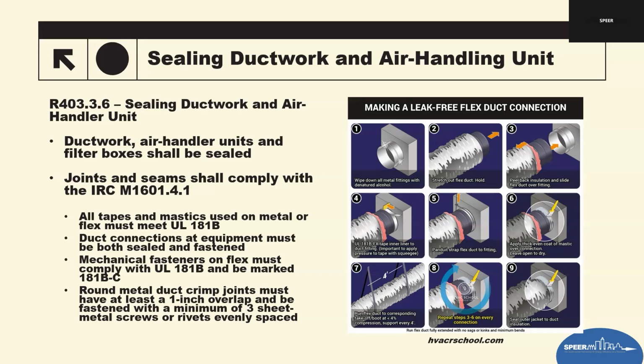So sealing alone is not enough. The joint must also be physically secured. Mechanical fasteners on flex duct must comply with 181B and be marked as 181B-C. This ensures strap ties used on flex ducts are approved for HVAC use.